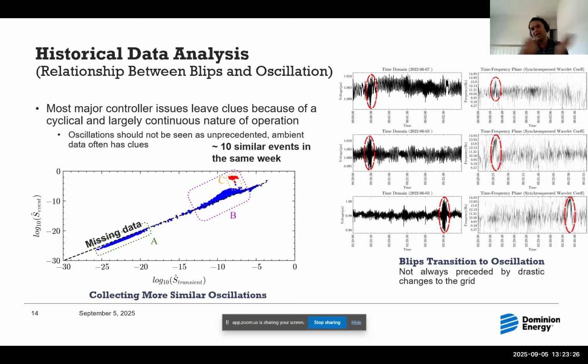It's the same signal in the time-frequency plane, zoomed into the 9 to 15 hertz range. In all these events, there's dynamics around 10 to 11 hertz showing up as periodic bursts of power, which lead to an oscillation, and during the oscillation period those dynamics vanish. This is common across all the similar events we've seen at that location.